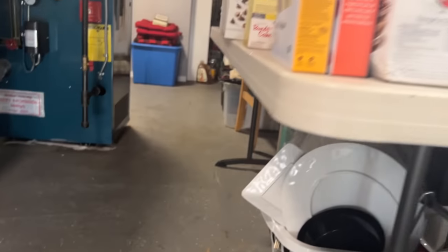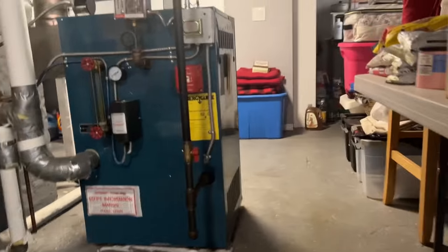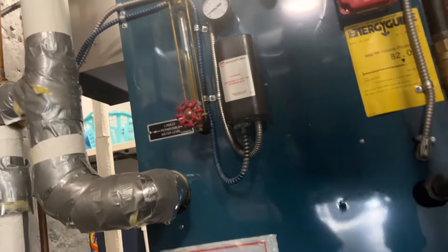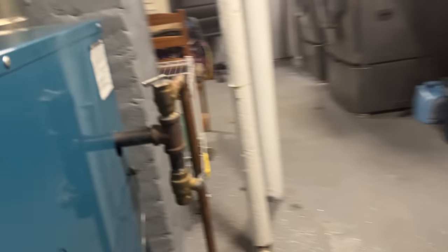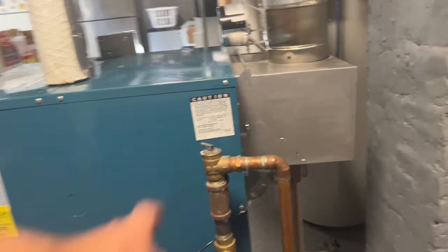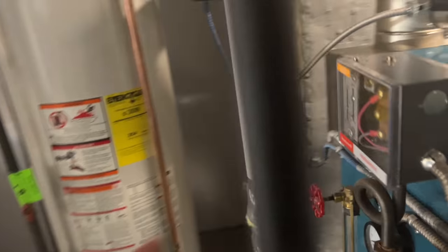I think we did your water heater, right? So what's going on? Let me turn it on so you can see what happens within about two minutes. Burnham - I can see there's a damper, 15 PSI relief valve, boiler drain, pressure trol, sight glass, low water cutoff, transformer.